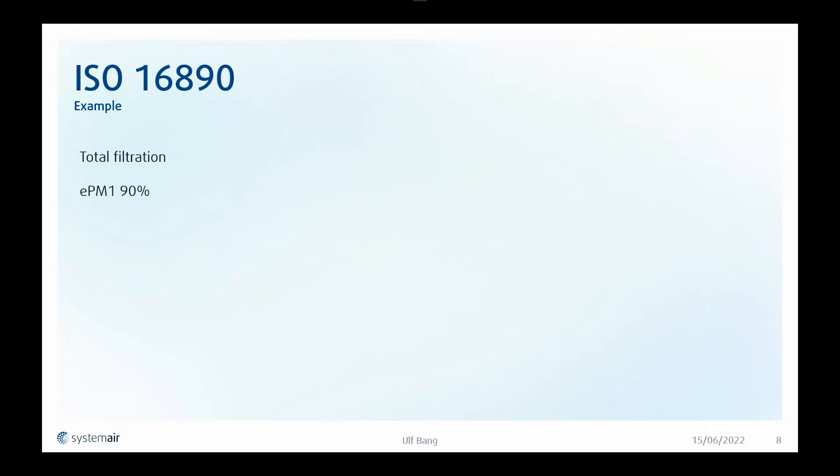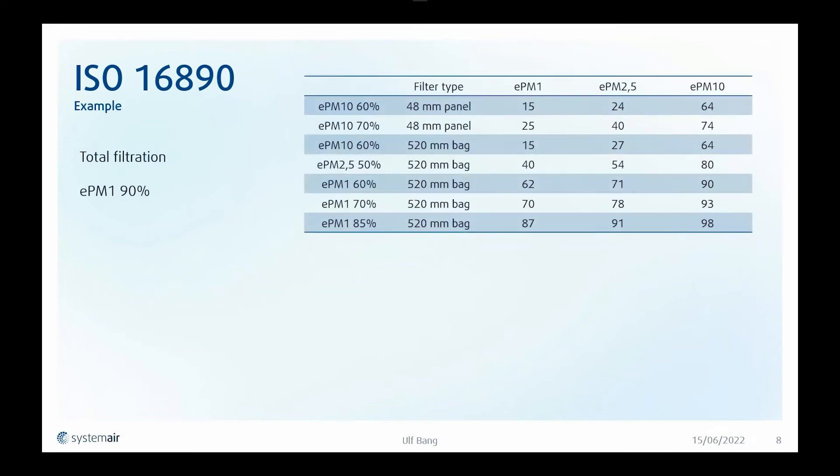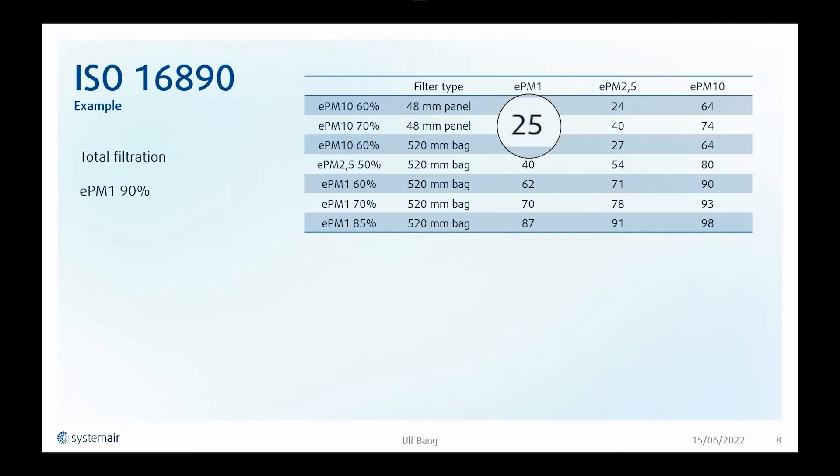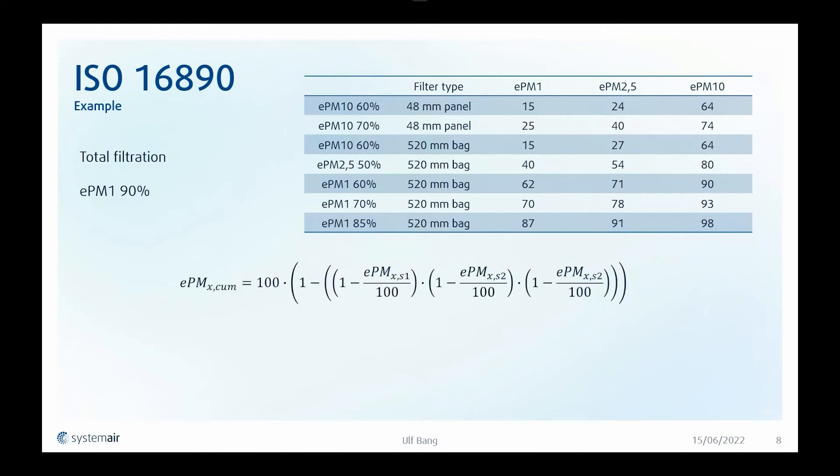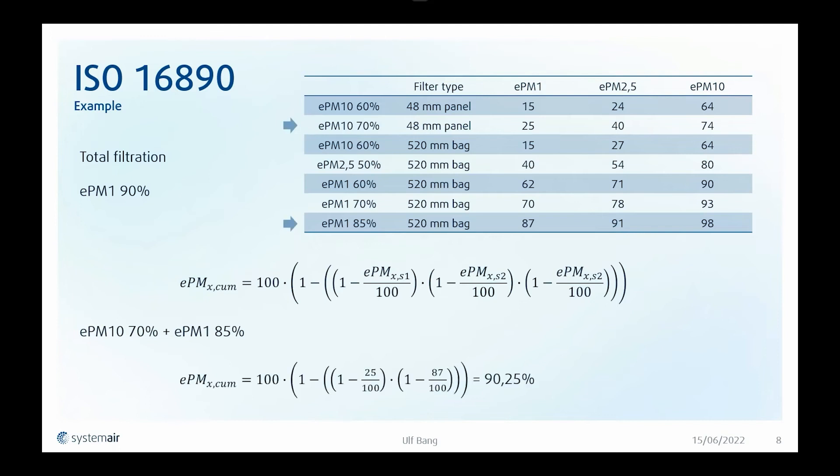I am aiming to have a total filtration of EPM 1 90%, but even though a filter is EPM 10 70%, then it still filtrates some of the PM 1 particles. In this case, you can see that we actually have an efficiency of 25% for PM 1 particles, even though it is a PM 10 filter. If we calculate the total efficiency from this formula and we select a filter combination of an EPM 10 70% and EPM 1 85%, then we will see that we actually get a total filtration efficiency of 90.25%. And that is of course sufficient when our requirement was 90%.